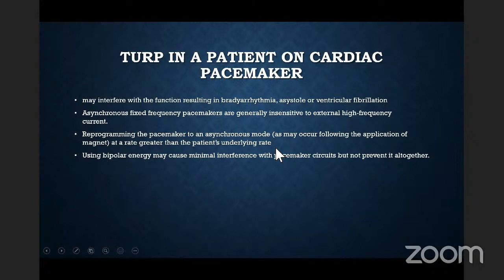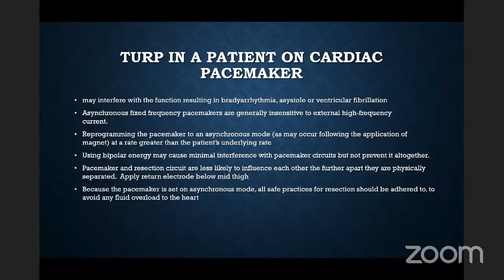Bipolar energy may be used with minimal interference with the pacemaker circuit, but does not altogether prevent it. So the same precaution has to be taken even with bipolar. Pacemaker and resection circuits are less likely to influence each other if they are further apart and physically separated. That is why the return electrode should be applied below the mid-thigh in such cases. And because the pacemaker is set to an asynchronous mode, now all safe practices for resection should be adhered to, because any fluid overload should be avoided for this patient's heart now, and the procedure should be completed in due time with all safety measures that we take.